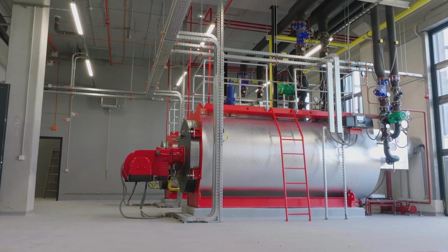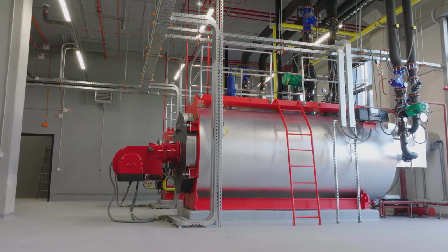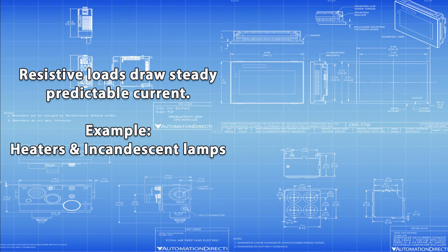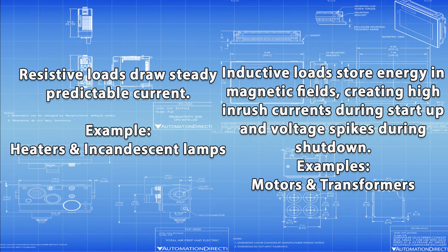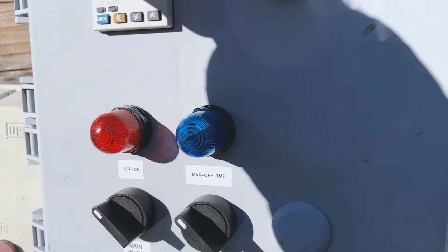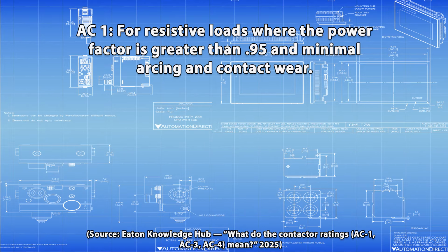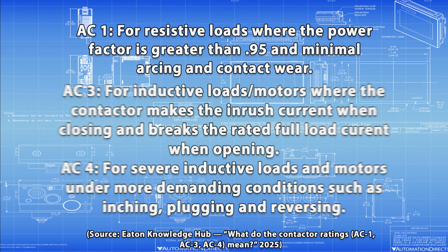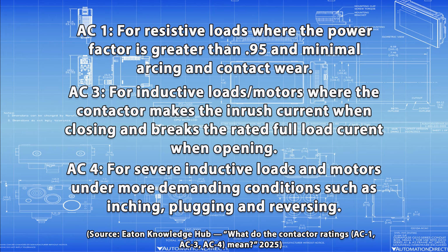Electrical loads aren't all the same, and contactors are rated accordingly. Resistive loads, like heaters and incandescent lamps, draw steady, predictable current, making them easier to switch. Inductive loads, such as motors and transformers, store energy in magnetic fields, creating high inrush currents during startup and voltage spikes during shutdown. These stresses create more wear on switching contacts, so contactors carry different ratings: AC1 for resistive loads, and lower rated categories like AC3 or AC4 for inductive loads, where both mechanical and electrical demands are higher.